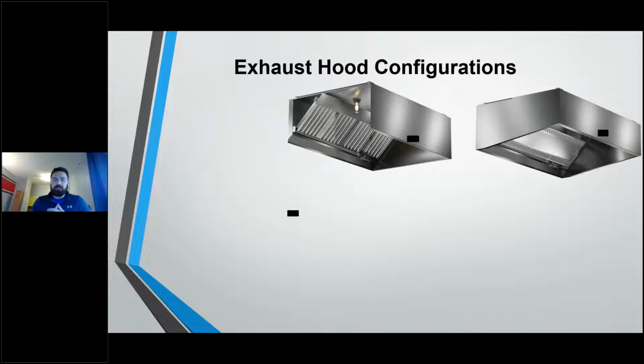And in that case, you're going to be looking for a tapered styled hood. Tapered styled hoods are going to typically come in anywhere from 18-inch fronts down to around 12-inch fronts. And again, the reason for that hood is you're still going to hang that at 80 inches above the finished floor as required by ADA, but it's going to lower your overall height of your exhaust hood system.